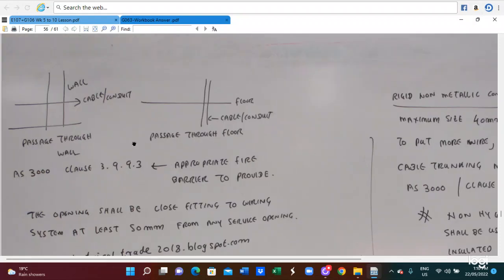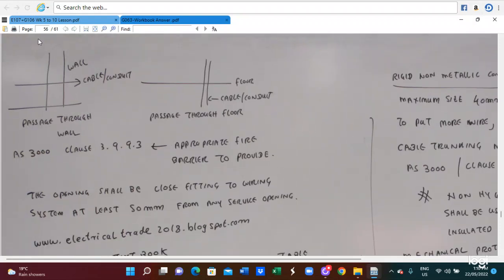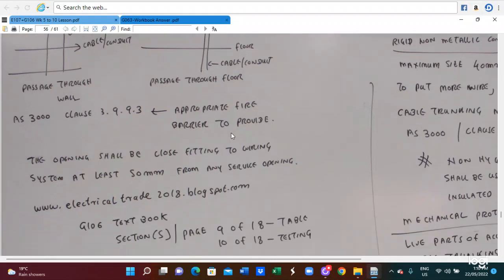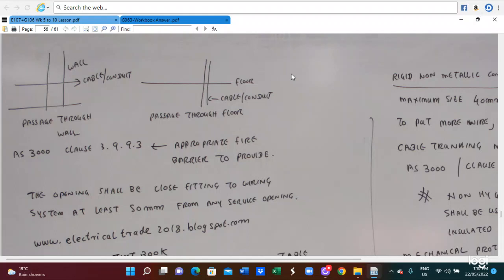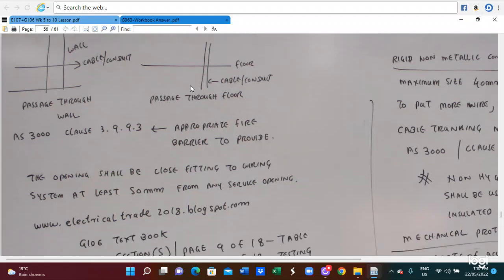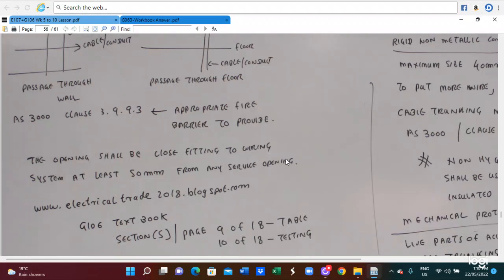So this is for the cable, and there's a conduit with a cable passing through the wall and the floor. In this case, this is passing through the wall, this is passing through the floor. If you want to pass a cable through the wall and the floor, we have to follow the AS3000 standard, clause 3.9.9.3. Appropriate fire barriers need to be provided.